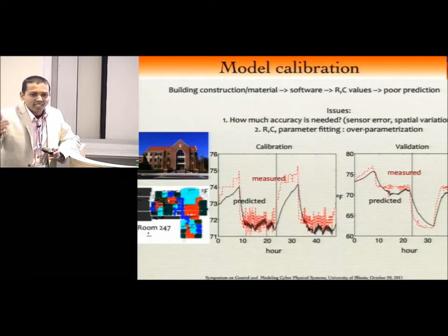Now the question is how do you do this calibration? Because every wall has 3 R and 2 C parameters, so 5 parameters per wall. With 4 walls, you get 20 parameters, but you only have one output to match. So it's a highly over-parameterized problem — almost any R and C values you pick can match the data.